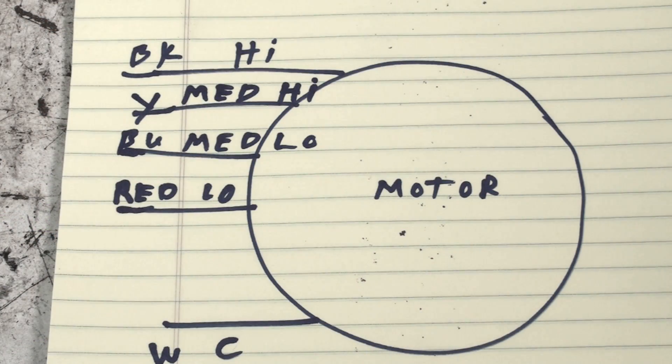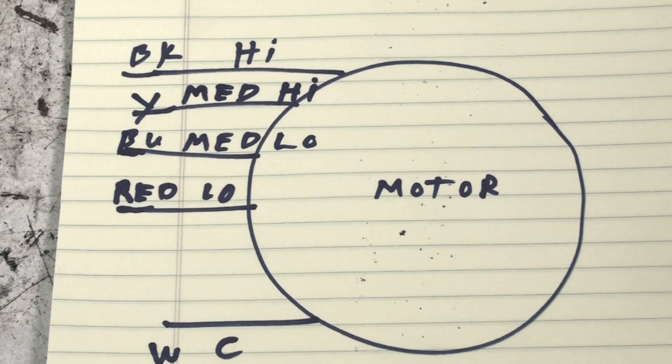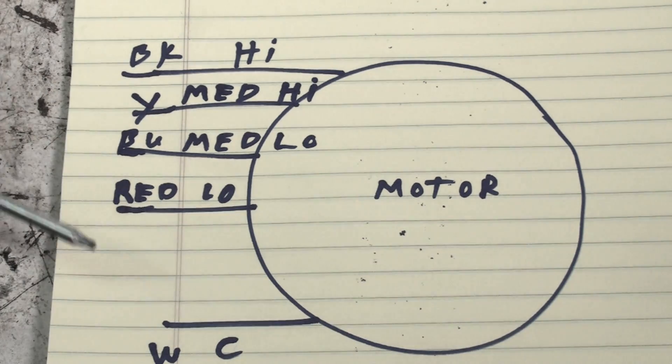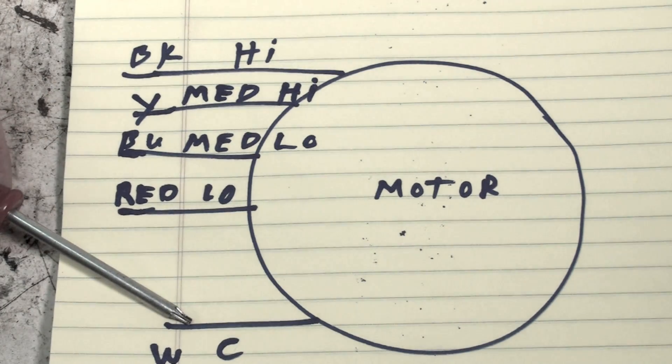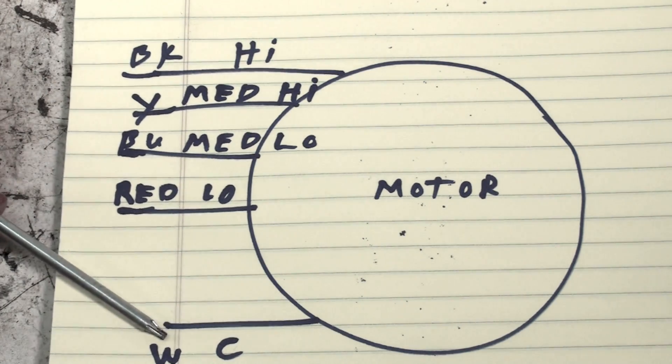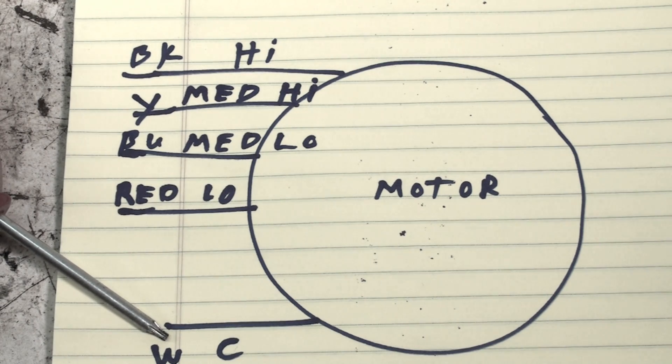I had a question about changing speeds on a gas furnace blower. I wanted to start out by explaining that a multi-speed blower is going to have a common wire. Most of the time the common is white.